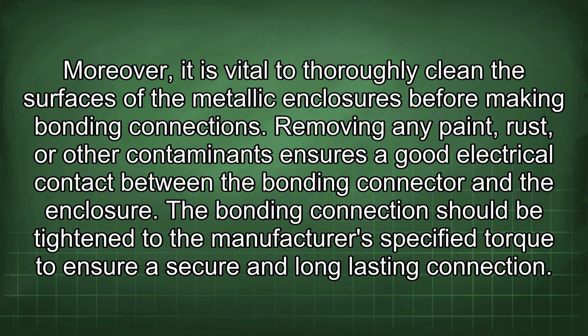Moreover, it is vital to thoroughly clean the surfaces of the metallic enclosures before making bonding connections. Removing any paint, rust, or other contaminants ensures a good electrical contact between the bonding connector and the enclosure. The bonding connection should be tightened to the manufacturer's specified torque to ensure a secure and long-lasting connection.